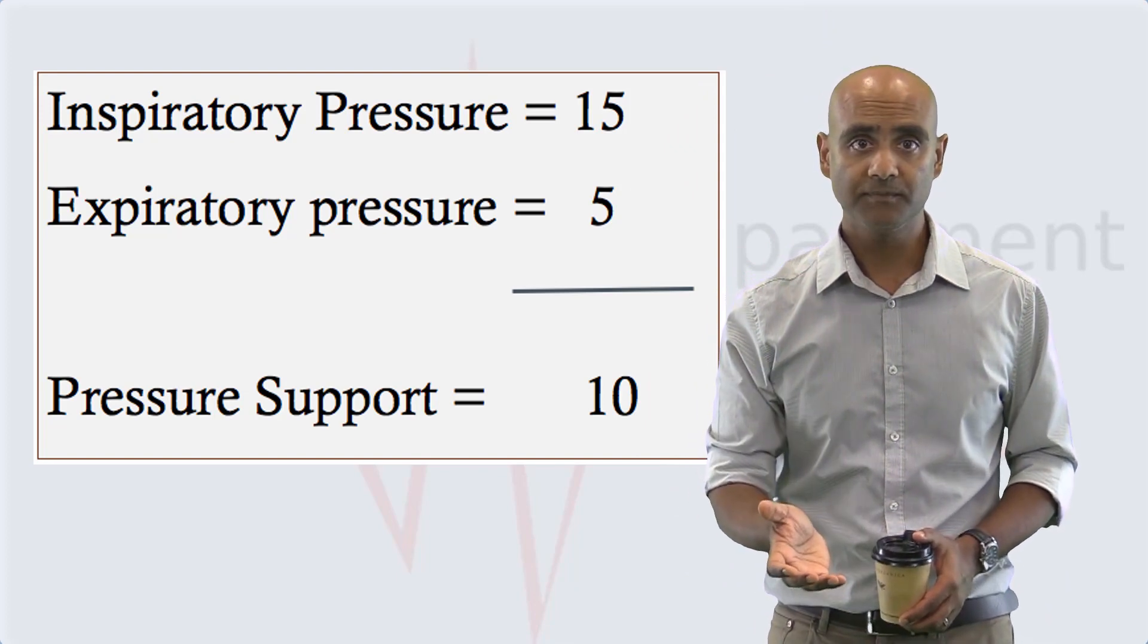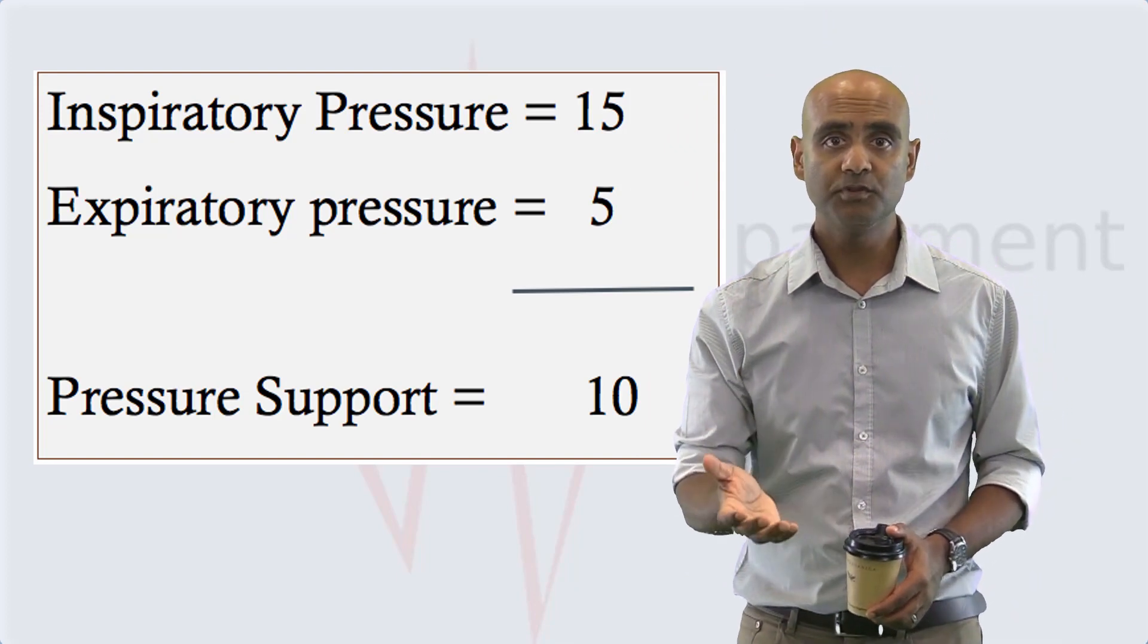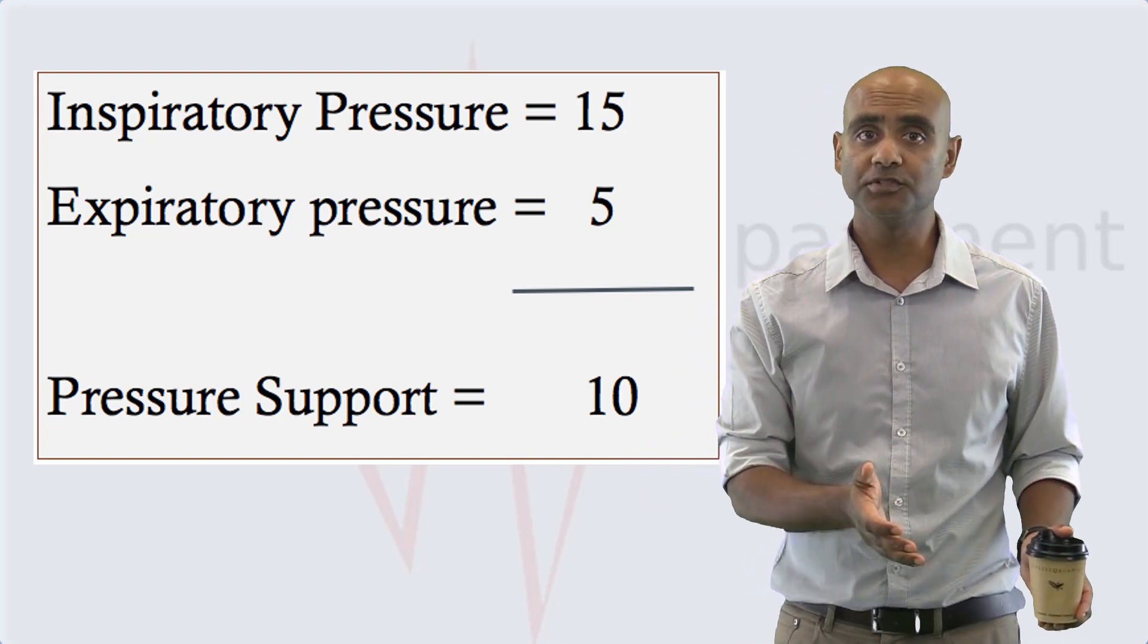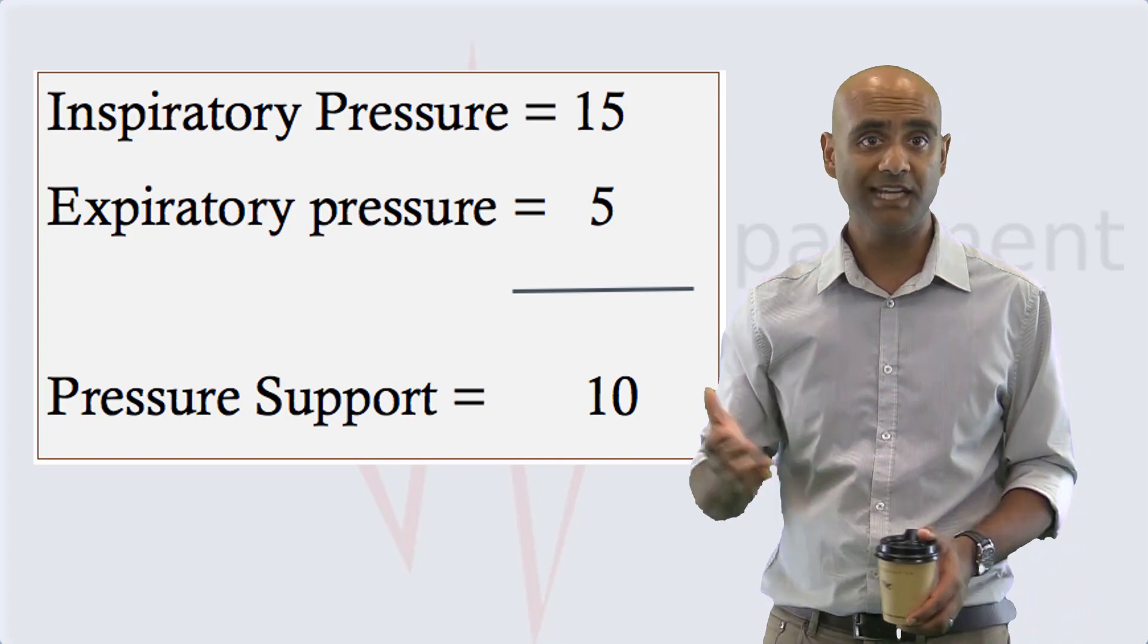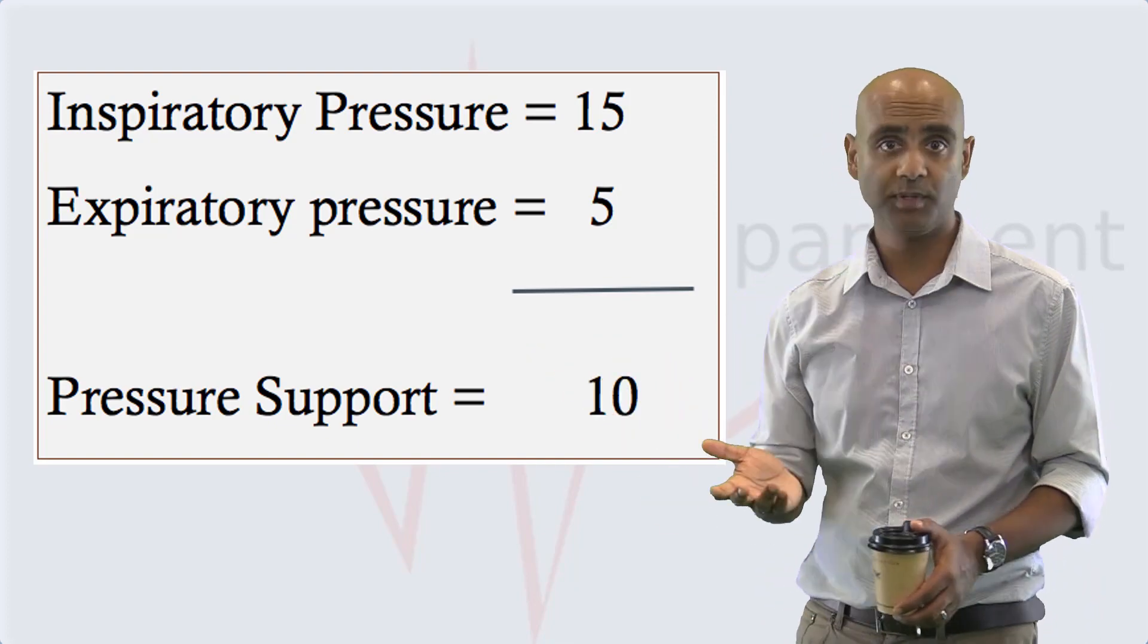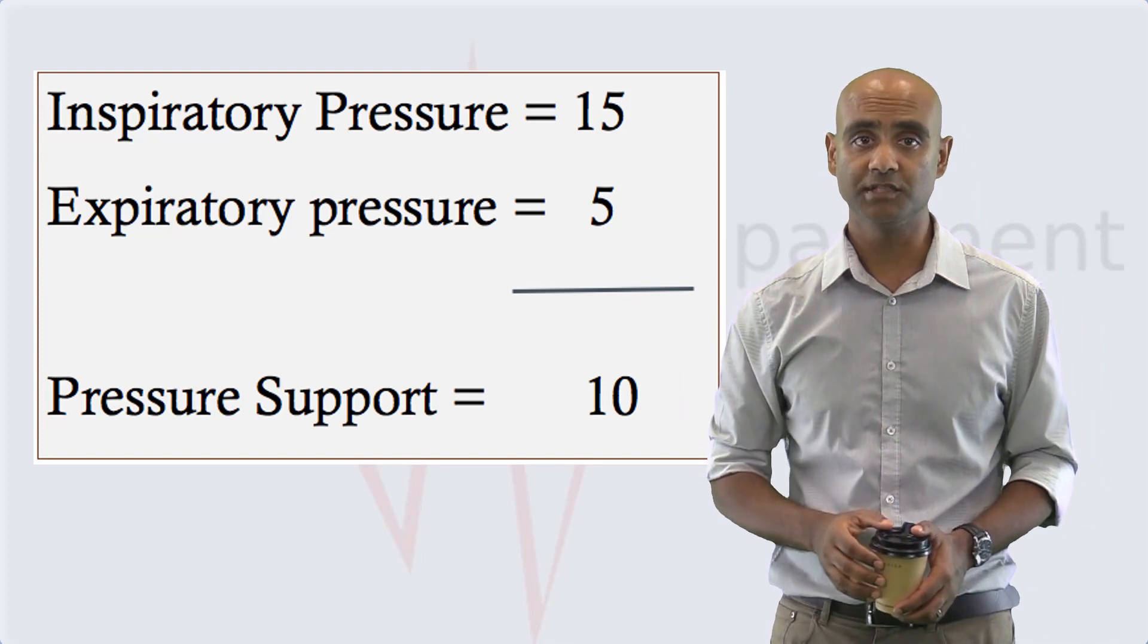As you can see, setting an inspiratory pressure of 15 and an expiratory pressure of 5 now produces a pressure support of 10 centimetres of water, as compared to the 6 centimetres of water he was receiving previously.